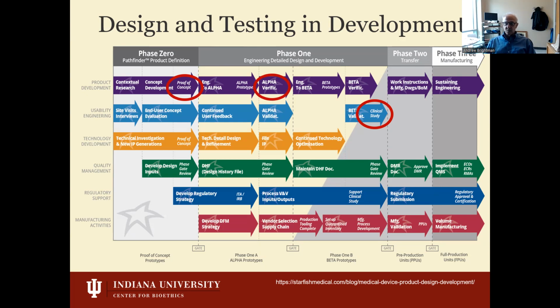There's alpha or early stage prototype verification of design inputs and validation of design outputs, and then a secondary or iterative process to the final product in the beta verification and validation. It's at this point that it's called a design freeze, and the technology can't really be changed from here on out through clinical study, through approval, and into clinical use. If there's going to be a significant change of any sort to the way the device is designed, functions, or manufactured, or even to the quality management system, you may have to go back to approval stages and document every change and its impact on safety and effectiveness.